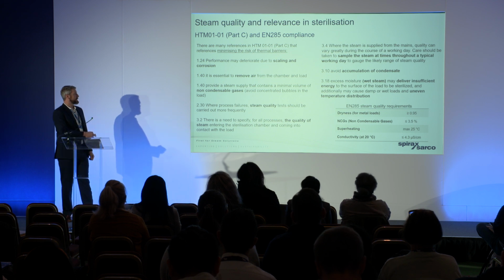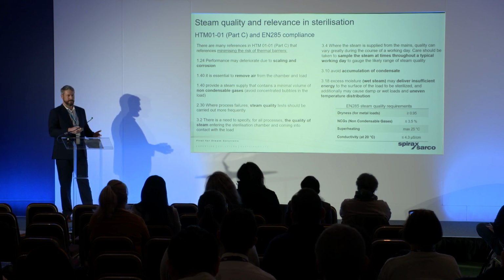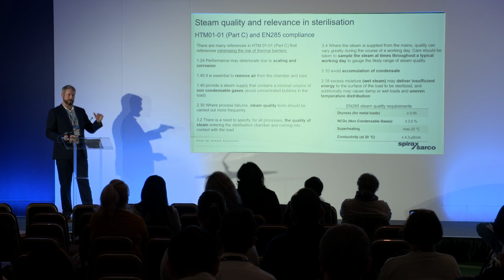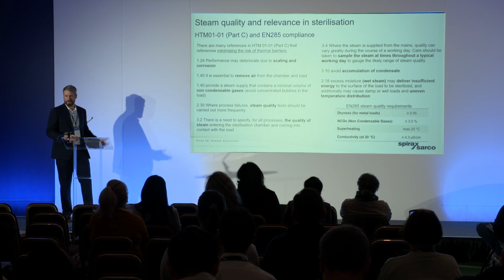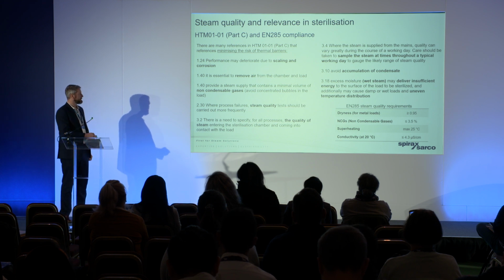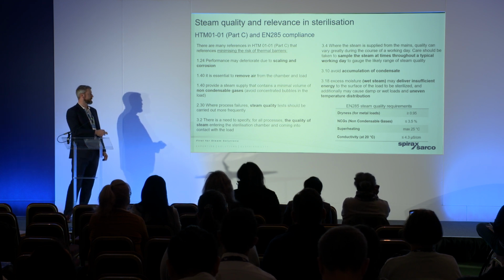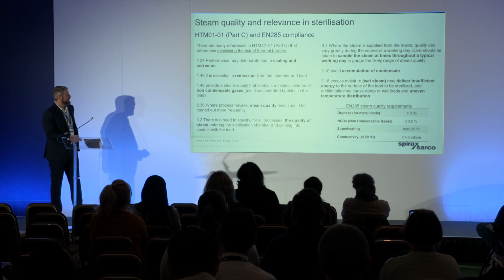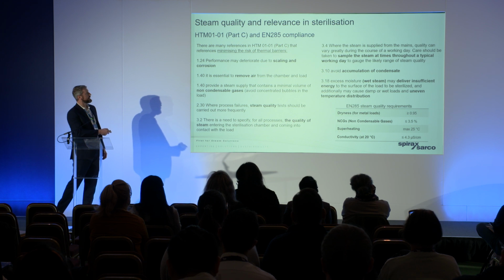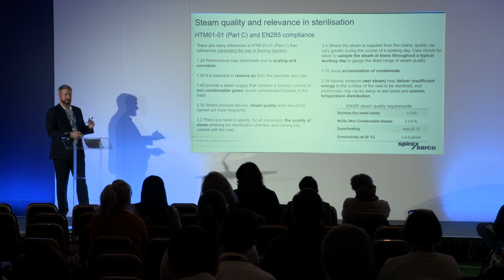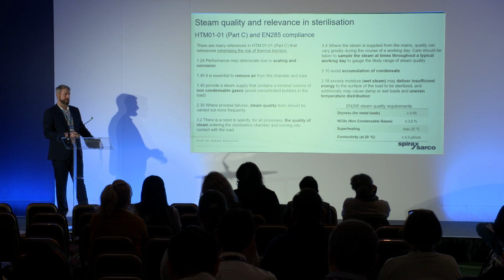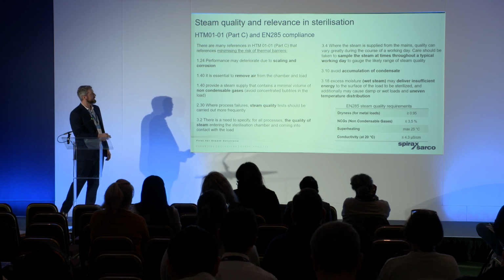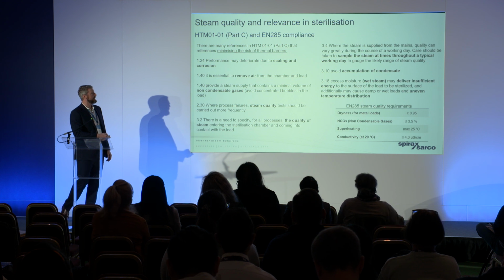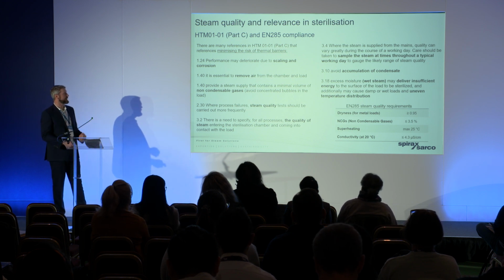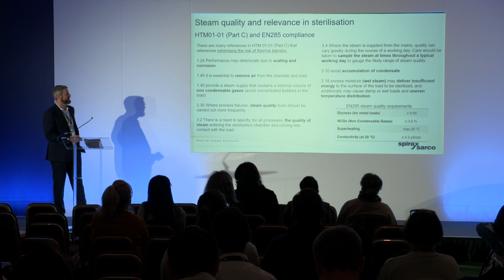It talks about steam quality tests being carried out frequently, especially where there are different dynamic loads and demands on that throughout the hospital for steam, making sure that quality is always good before the sterilizers. Again, quality of steam and testing, avoiding accumulations of condensate and water, because that can also create that barrier to heat transfer. And avoiding wet steam, because that will be insufficient energy to the surface of the load to be sterilized.